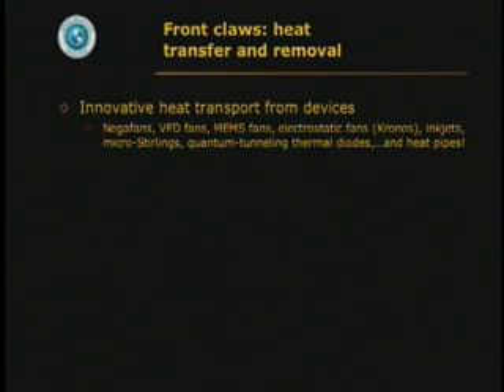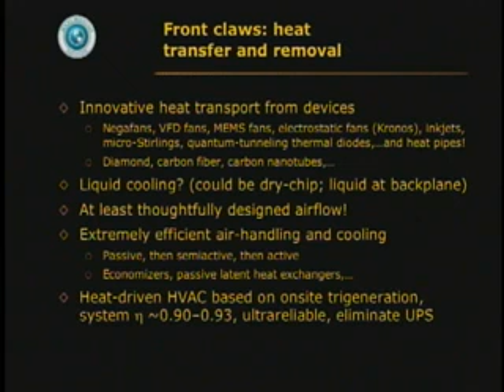The front claws of the lobster are heat transfer and heat removal—thoughtfully designed airflow, at least if you're doing it with air, very efficient air handling, very efficient cooling as I've described, heat-driven cooling based on on-site trigeneration of electricity, heating, and cooling, with system efficiency upwards of 90%. Then it's ultra-reliable, say with fuel cells, and you get rid of the uninterruptible power supply. And the other little bits of the lobster: the building envelope, the lighting.